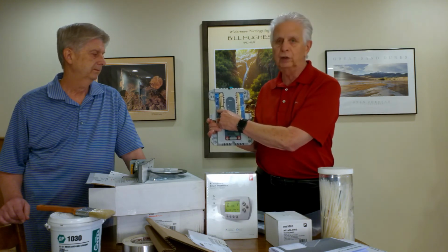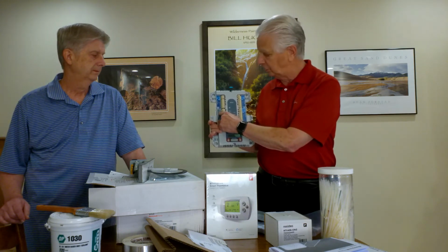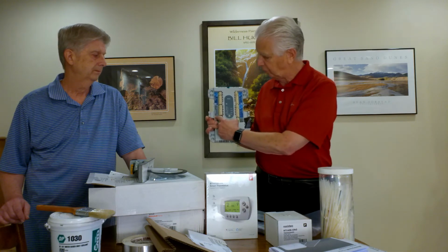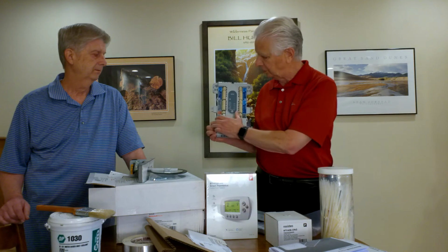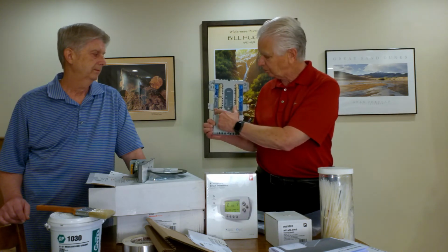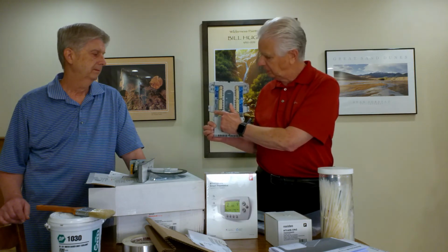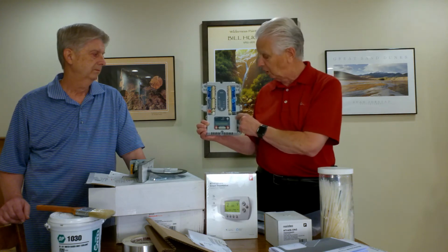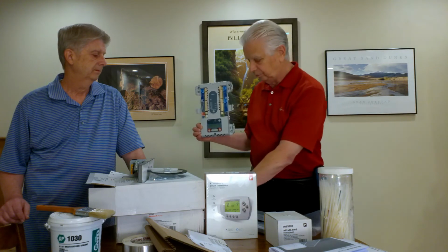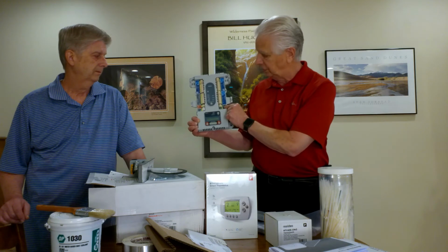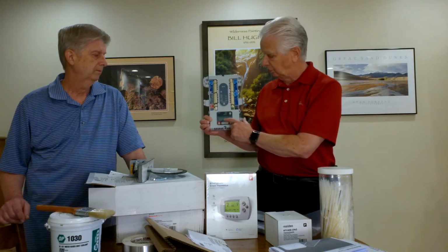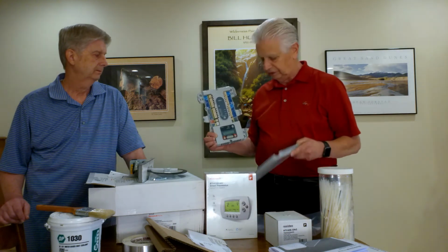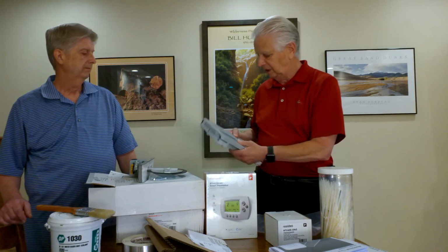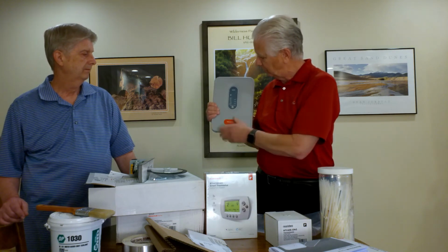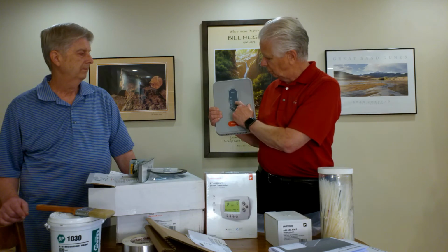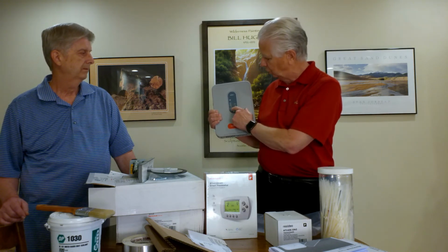To the equipment, which would be your furnace and air conditioning or heat pump if you're using this on a heat pump. Power from your transformer in. If you're using wireless thermostats, then you need additional equipment. That is Red Link, and it would wire in here. Then you don't need to run wires up to the second floor. The temperature sensor wires in here. Use this area to do the controls and set up, and then you can close it off, out of the way, and you get little lights here as the system operates. Tells you which zones are on, and whether it's heating or cooling, or if it's purging.